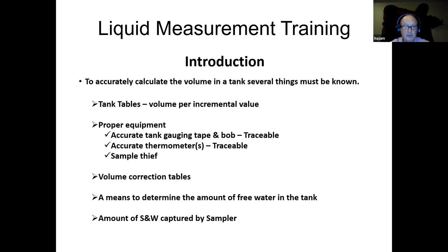We need the volume correction tables that we just talked about a few minutes ago. We have to have a means to determine the amount of free water in the tank. So therefore, that is also a gauging process. And like I said earlier, if we capture a sample of the water, entrained water and sediment as we're loading the vessel or the tank, we'll need a sampler to do that.